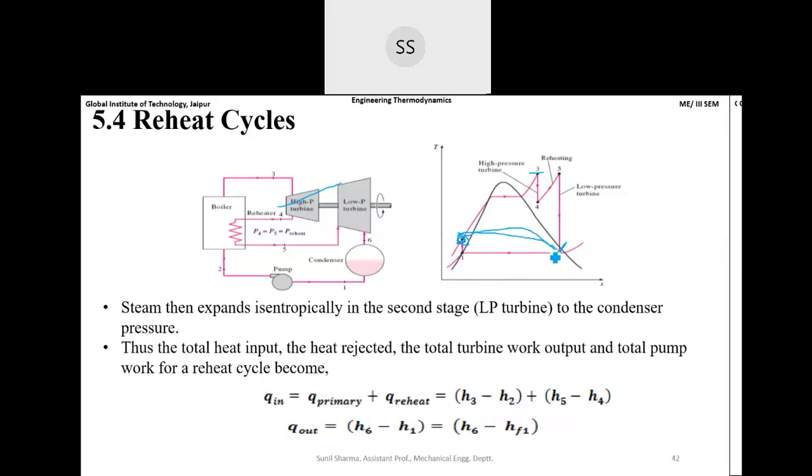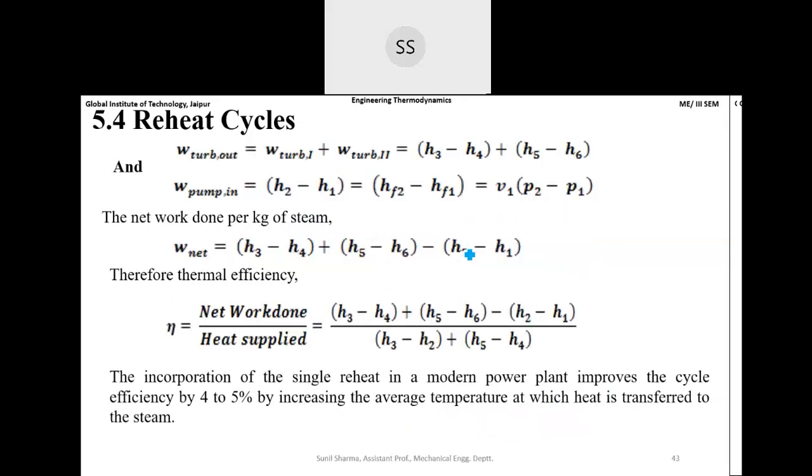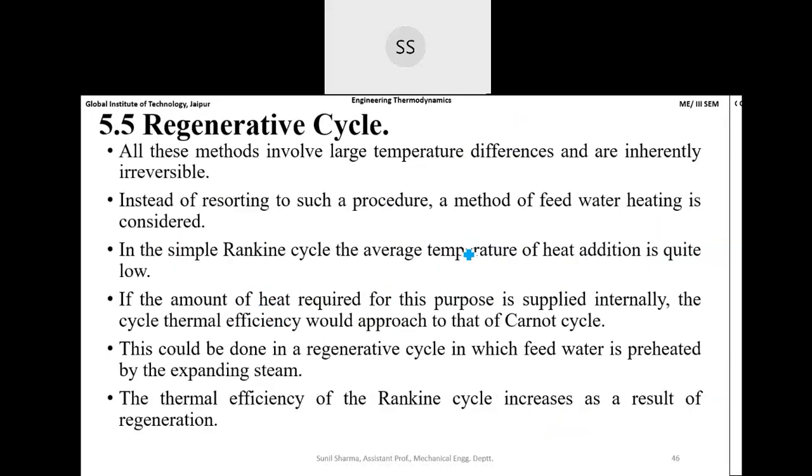Okay. So in that case, you do two things. First, you are heating the water. Second, by preheating the water, which is going into the boiler, आप यहाँ पर de-aeration कर रहे हैं। तो ऑक्सीजन और CO2 जो dissolved gases हैं, आप उनको remove कर रहे हैं, ठीक है। And both are healthy for the better running of the power plant.